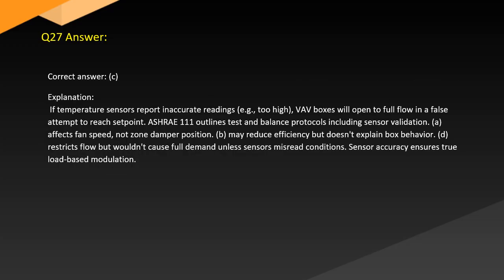Answer. Correct answer: C. Explanation. If temperature sensors report inaccurate readings, for example too high, VAV boxes will open to full flow in a false attempt to reach set point. ASHRAE 111 outlines test and balance protocols, including sensor validation. A. Affects fan speed, not zone damper position. B. May reduce efficiency but doesn't explain box behavior. D. Restricts flow but wouldn't cause full demand unless sensors misread conditions. Sensor accuracy ensures true load-based modulation.